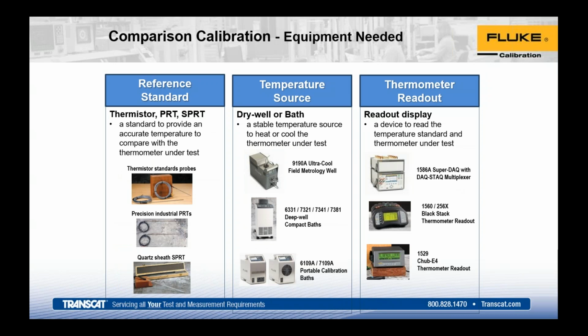Once you move past the fixed point cell, you get down into comparison. It's the same methodology. You're going to have a reference standard now. Typically, you'll have some sort of probe, which can be an SPRT as your reference, or if you're in a dry well, maybe something a little more industrial grade. But then you're also going to have your temperature source, which is more responsible for your stability, uniformity, and the heat. And then you've got to connect your probe to some sort of digital readout to interpret the resistance and convert it to temperature. So now you have three pieces, basically a probe, a readout, and a heat source working in conjunction to provide you a known, stable heat source that you can put other devices under test in and get the respective resistance or temperature out of.